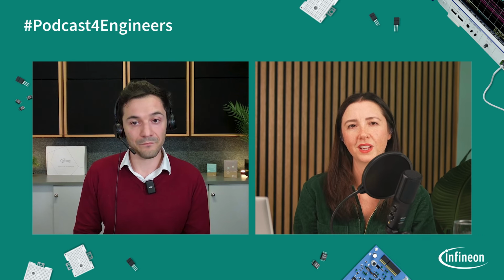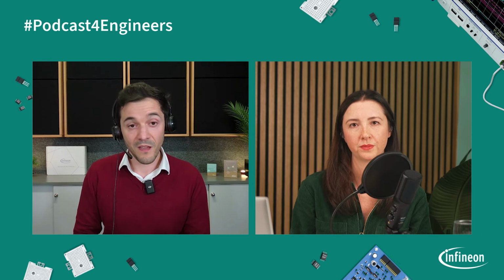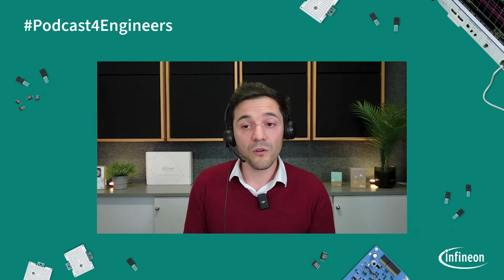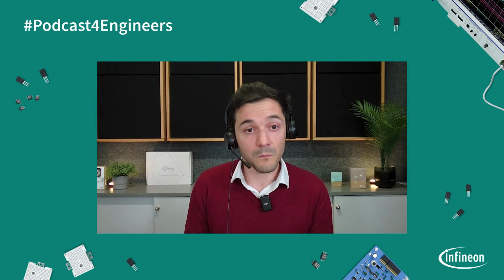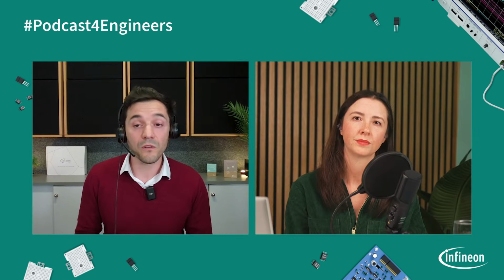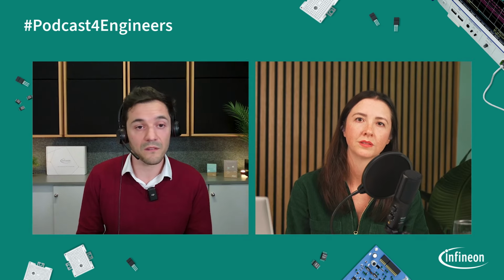And how can 48-volt architecture help with this problem? It's actually very simple from one perspective, I-square R losses. The power goes into this board from the bus rack. So if you have a reduction of 4 times of current, you have 16 times less I-square R losses. Very simple calculation. Moreover, the filter design is much simpler from 48 volt. And in general, this turns out to be a lower total cost of ownership for our end customer. So 48 volt is really important and is becoming a standard.